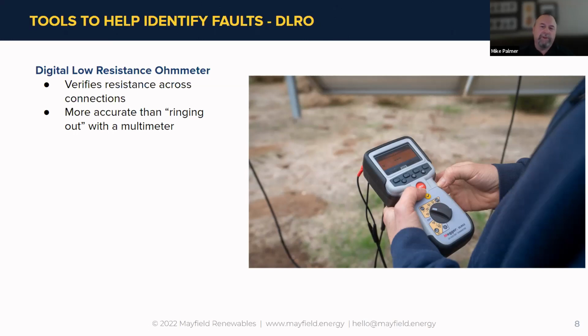And also what we really need to zero in on is technicians' safety in the array. Probably a term you don't hear a lot of. When it's lightning 3 miles away from the array you're in, you're still at risk because of ground potential rise. So these are all things we're going to talk about in more detail. You'll see in the coming year, especially at NABCEP. So that's the best I could tell you with limited time today on DLRO testing. Nobody's doing it unless it's inside the inverter, maybe on bus bars for both grounding and power cables.